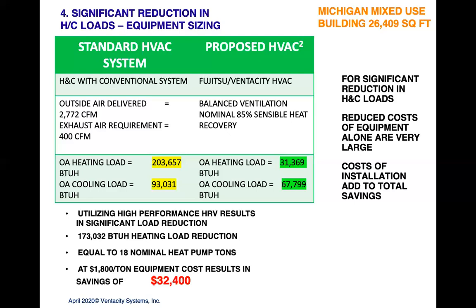If you apply this model correctly, and for those out there that are engineers and look at these projects, the old conventional, well, we'll look at about 400 square feet per ton for our heating cooling loads. When you use very high efficiency heat recovery for your outside air load and reduce it by dramatic amounts, in this case 85%, then your resultant heating cooling loads are impacted very, very positively. And now instead of 400 square feet per ton, we're typically looking at 600 square feet per ton in New England and about 700 square feet per ton in the Northwest, for example, British Columbia, Portland, Seattle, Northern California. So it has a really big impact on reducing the cost of your heating cooling system when you use very high efficiency heat recovery for your ventilation.